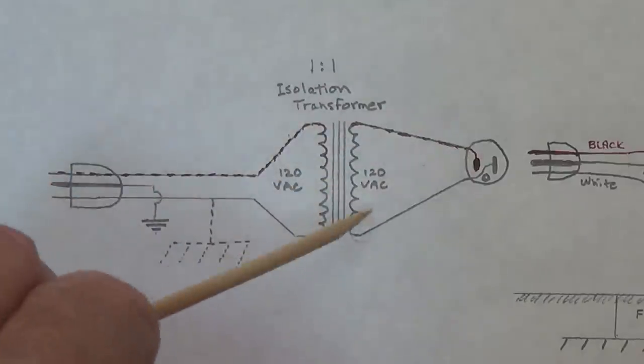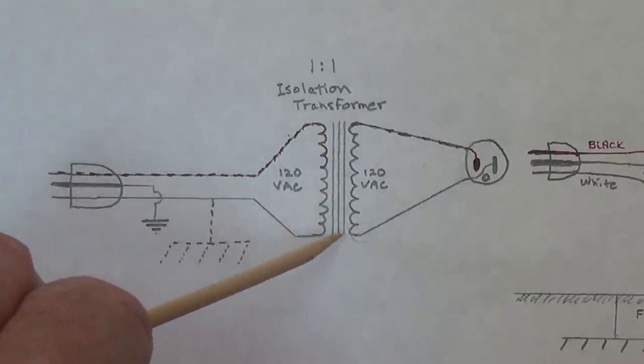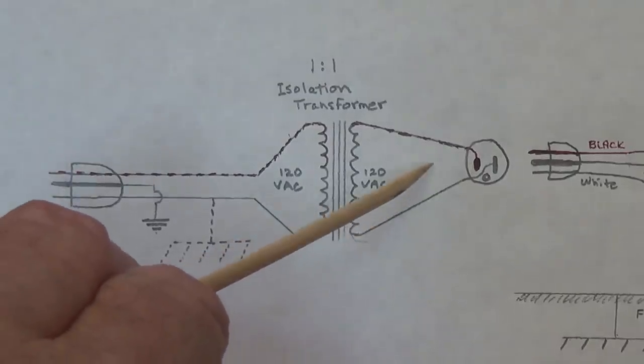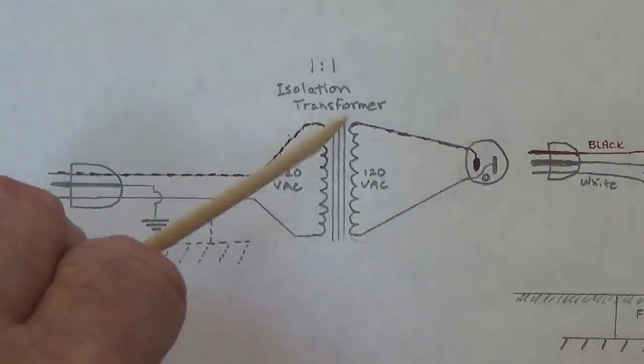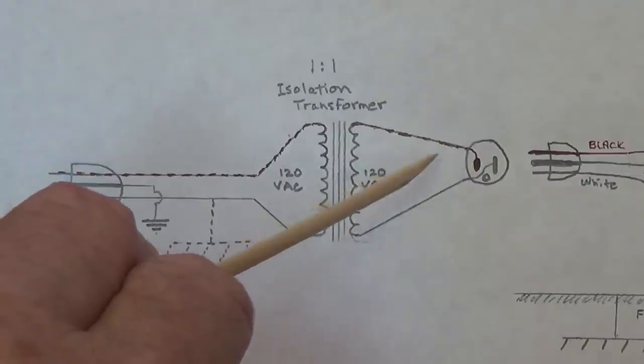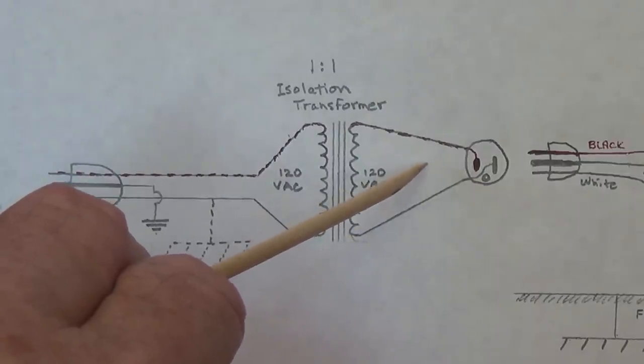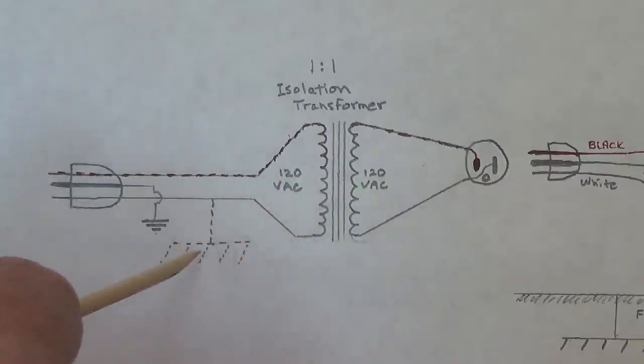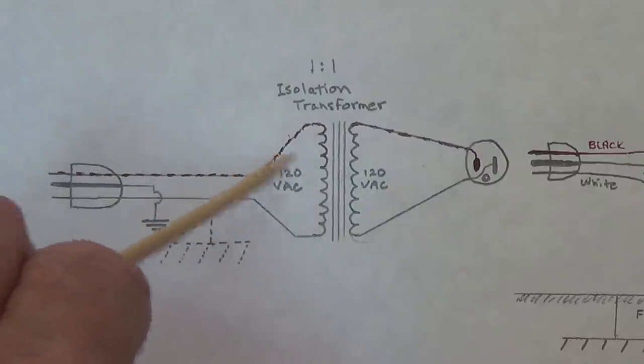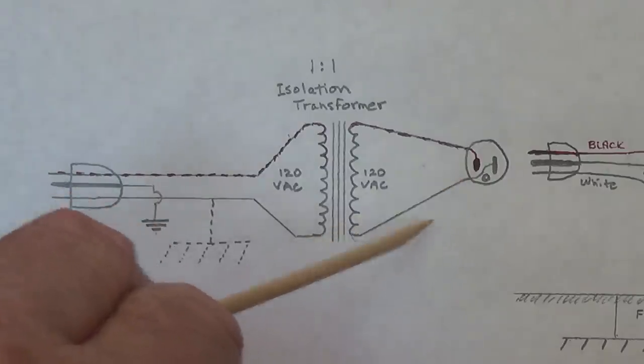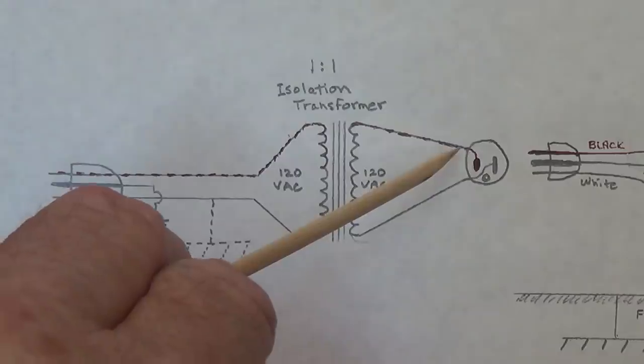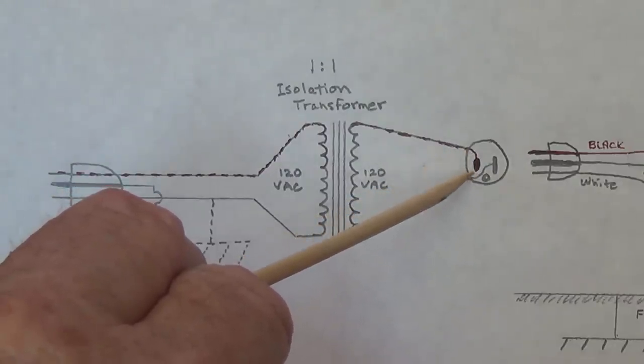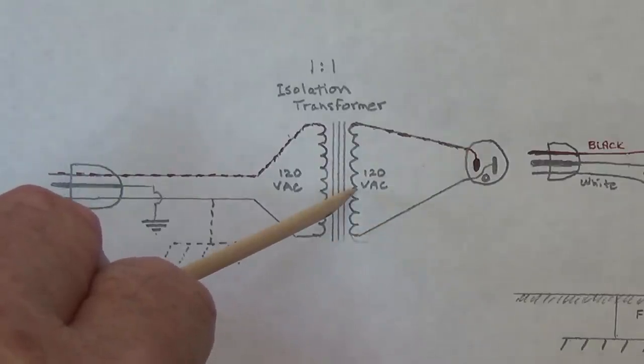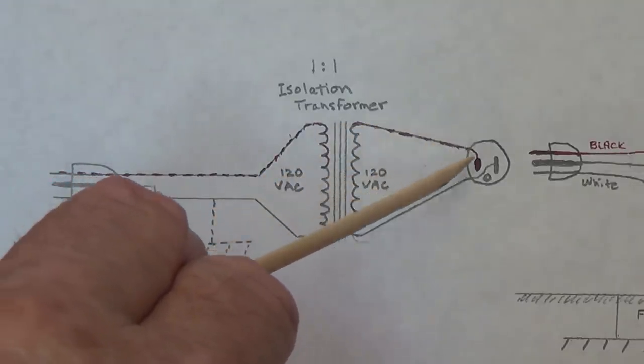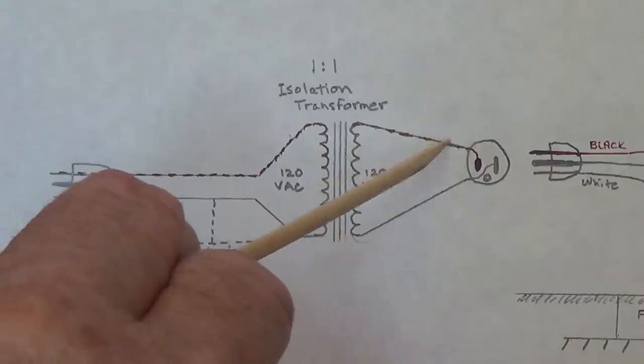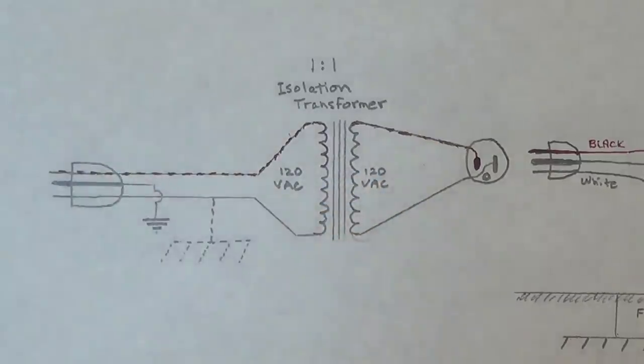But the secondary is very different. Because there is no connection here, no direct connections between this winding and this, there is no earth ground reference on this side of the transformer. This is very much like the secondary was in our amplifier. You see that the earth ground referencing is limited to the left side of the transformer and not over here. These horses, once they leave the transformer, don't want to go to ground. They don't want to go anywhere except back on this return line to the stable. And that's all they're going to do. So we have eliminated the possibility of touching with one finger anything in here while we're grounded and being killed.